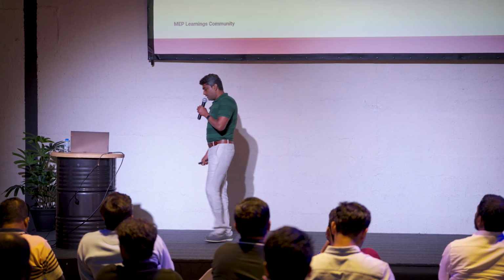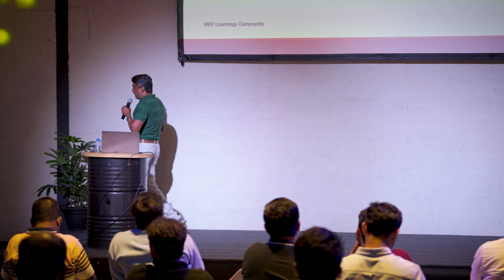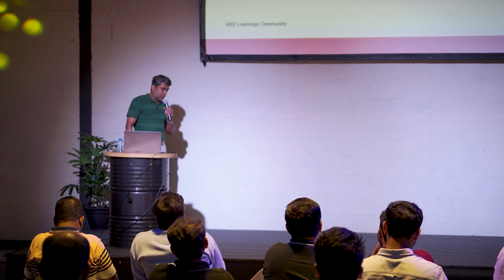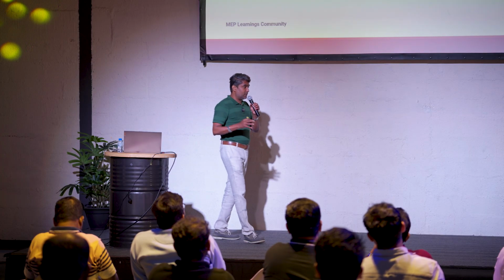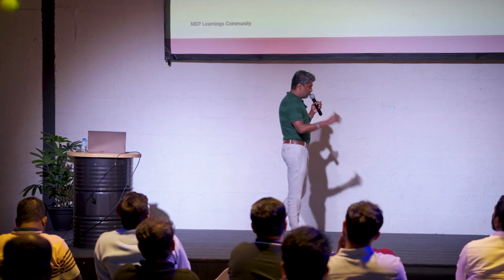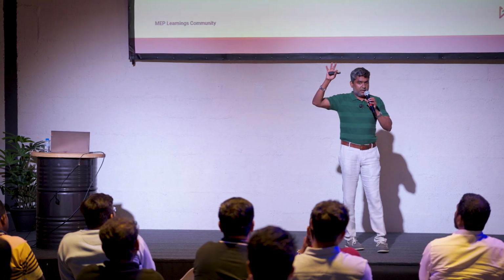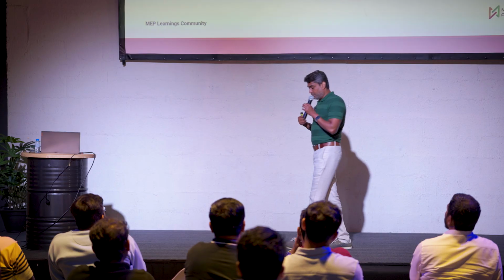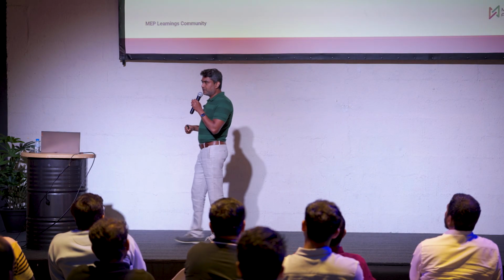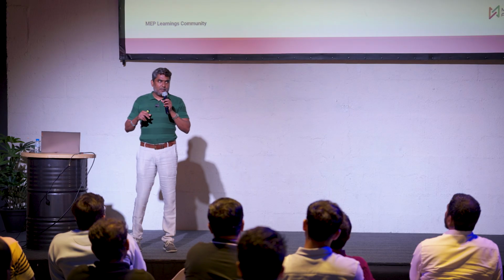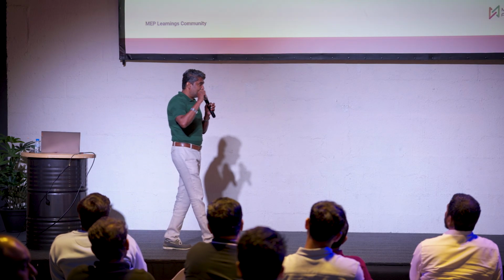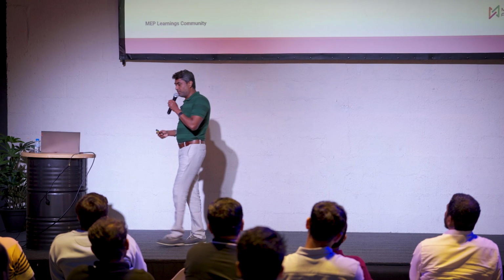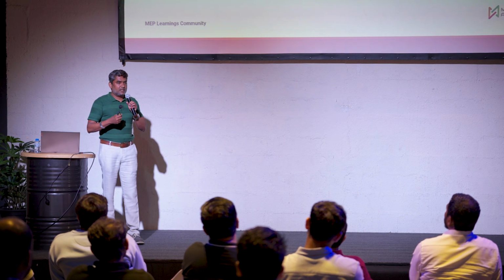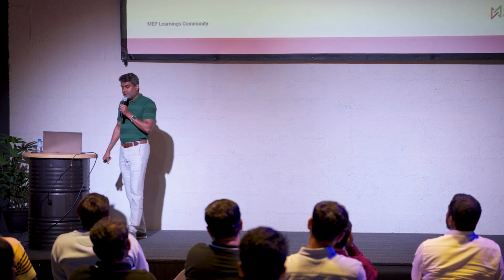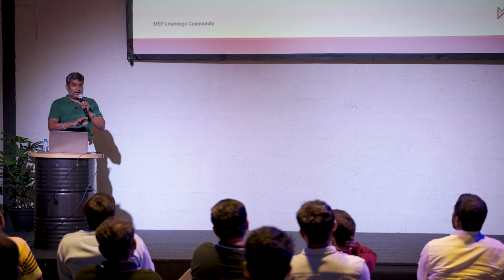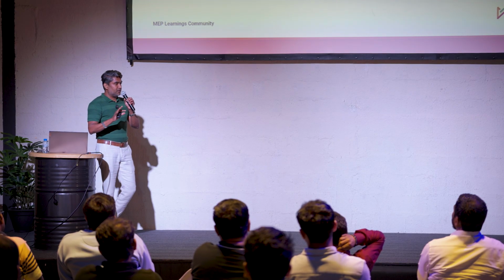When I talk about speech legibility, I don't know whether you've come across situations where you use sounders in some places and speakers as well. Imagine in this room, if you have a fire alarm sounder as well as a speaker—the sounder will keep ringing. As soon as fire is confirmed, the sounder starts alarming, and it's so noisy. At that time, if someone is trying to broadcast a message to people, obviously it's not going to be legible—the speech will not be clear to the occupants. For that reason, you should never mix these two notification devices together.